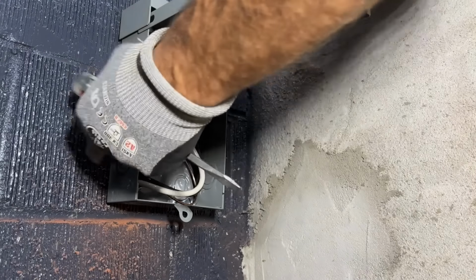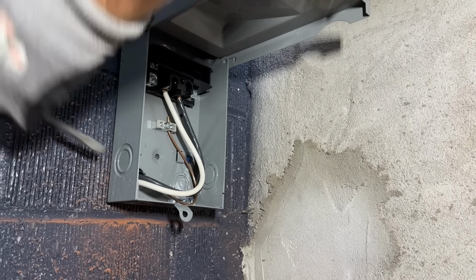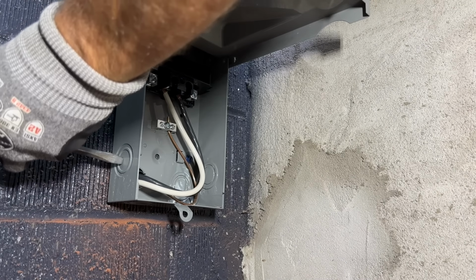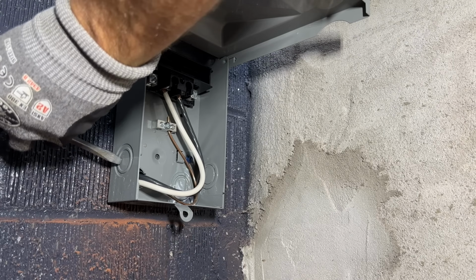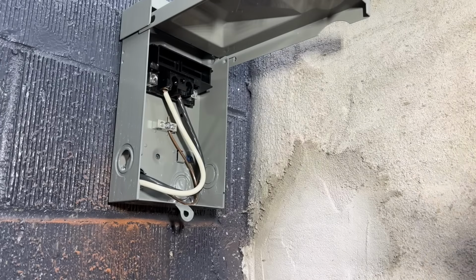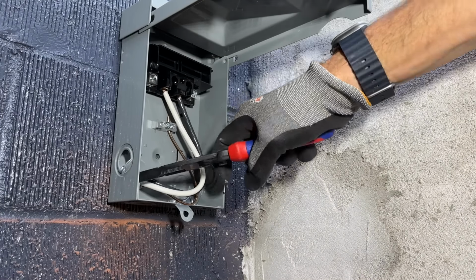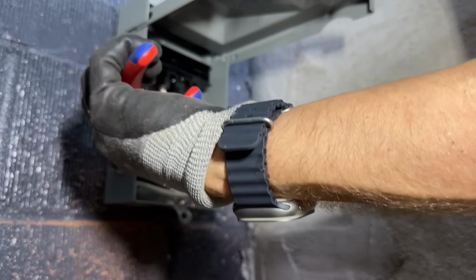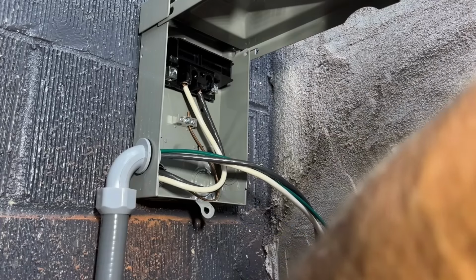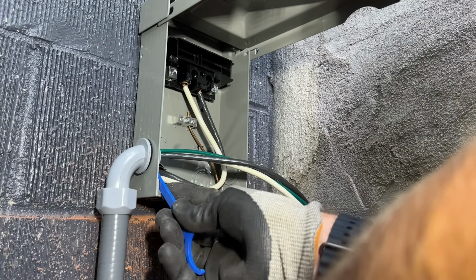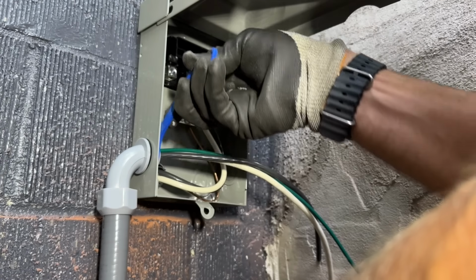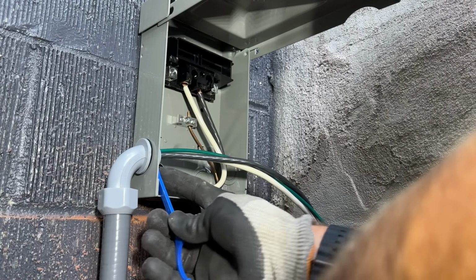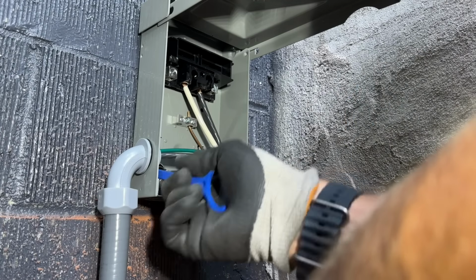So now we'll bring the liquid tight whip that will go from the disconnect up to our AC unit. So we'll just get this knockout out of here. And then I will angle this down just to help reduce the amount of moisture that can get into that fitting, and use my little 3/4 of an inch wrench here.